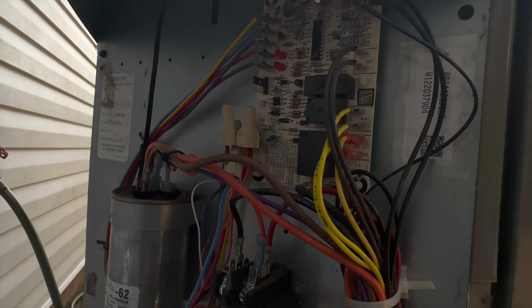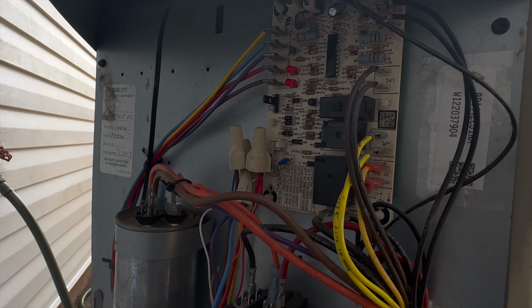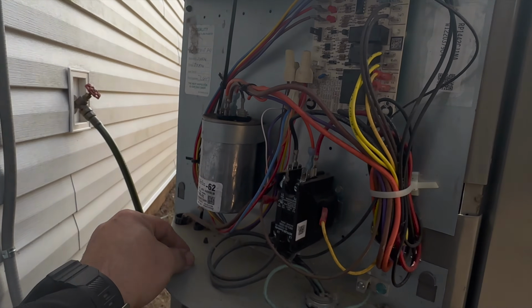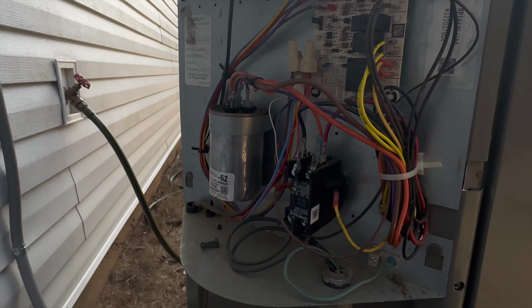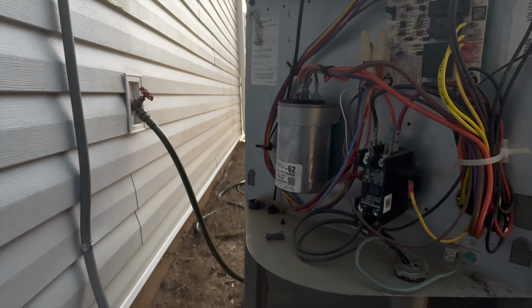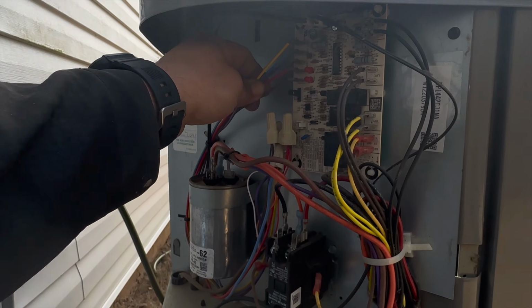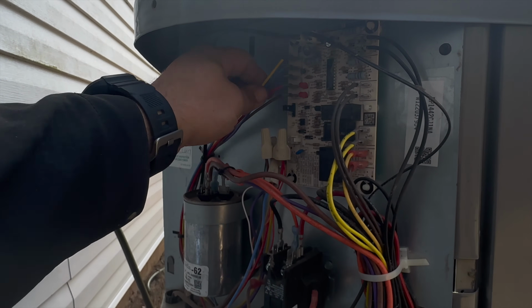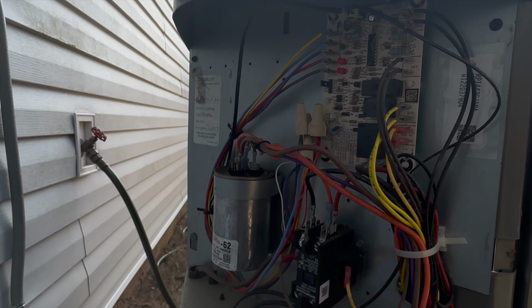Got probe set up. Let's see how the system's running. All right, so yeah, everything's working good inside, but our outdoor unit still isn't coming on. So we're gonna see why this isn't coming on and if we're getting some type of code. All right, so we are still getting a normal operation light. Everything inside says that it is sending the 24 volts here. So let's take a look. We'll check up here on this board to see what it's receiving from the zone board and the air handler.